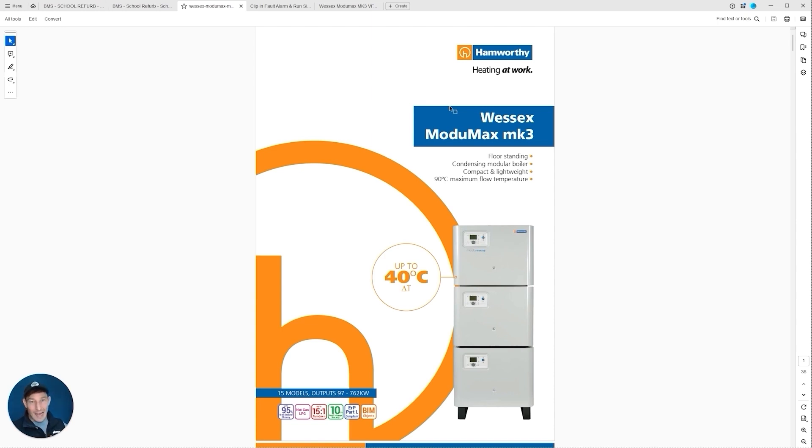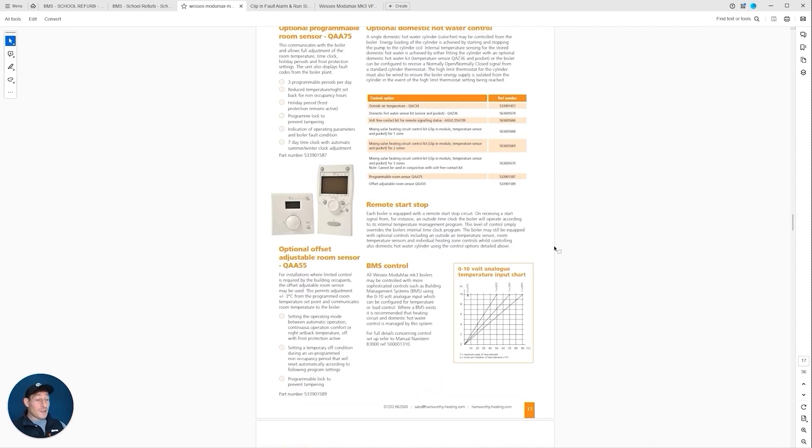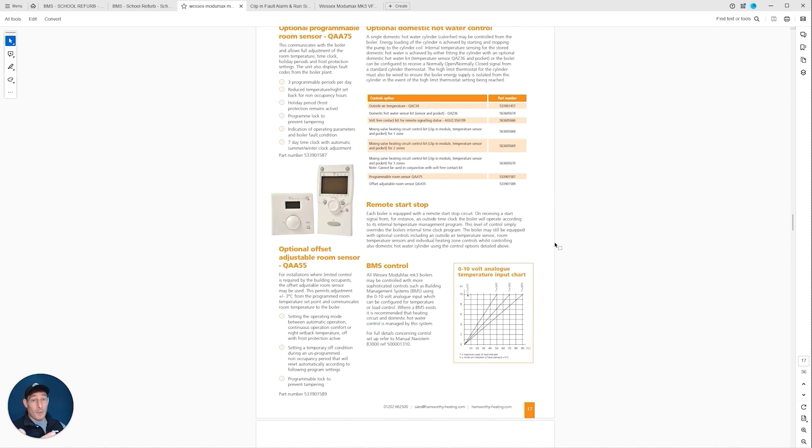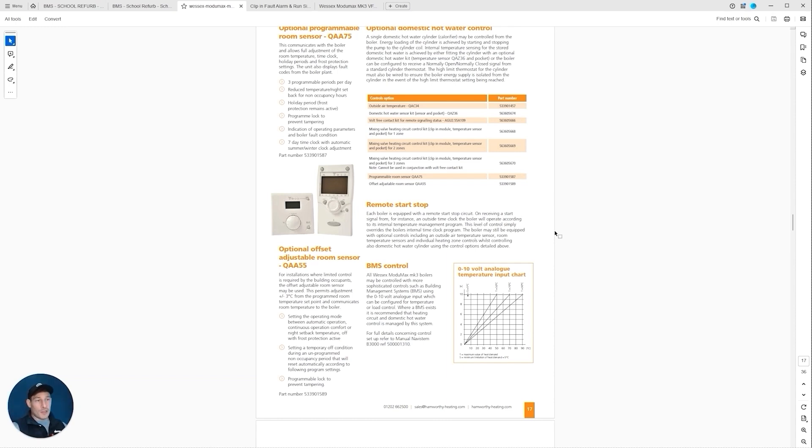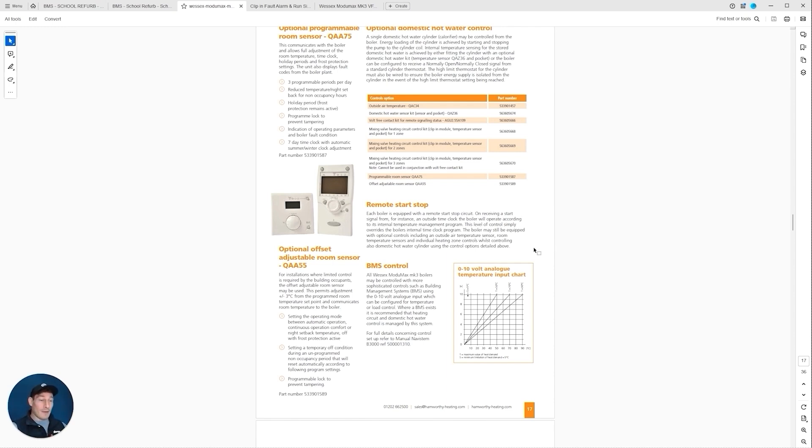For electrical connections, the first thing to mention is that this isn't just your standard on-off control that you see for boilers in most residential settings. Because this is a BMS and we want to be more efficient with how we're controlling the boilers rather than just being on and off, we want to be able to modulate—so change the heat output of that boiler—and that's where we're going to be using a 0 to 10 volt signal to do this.